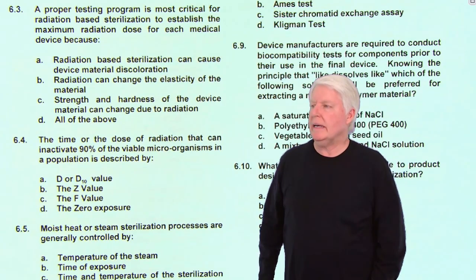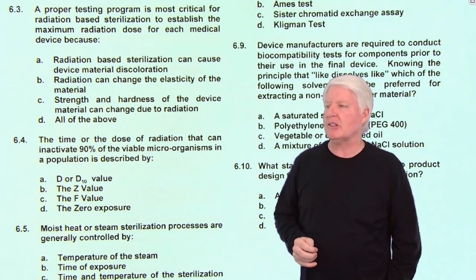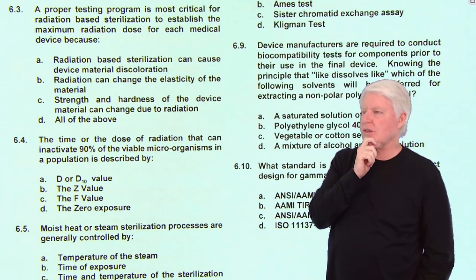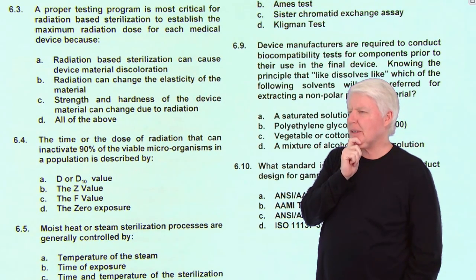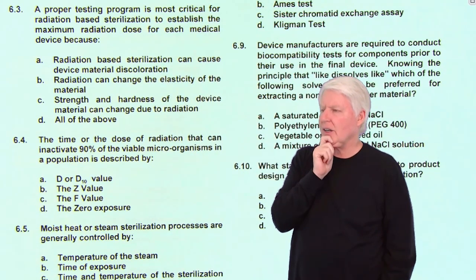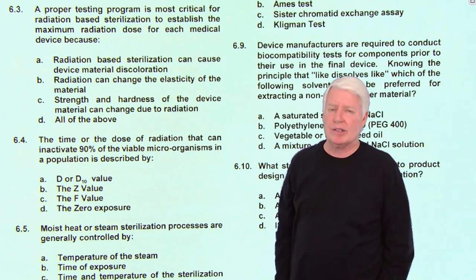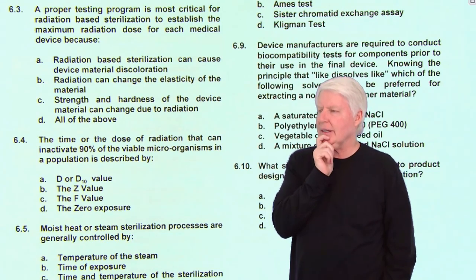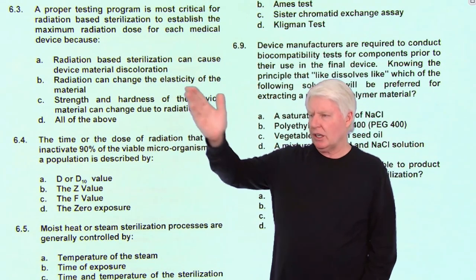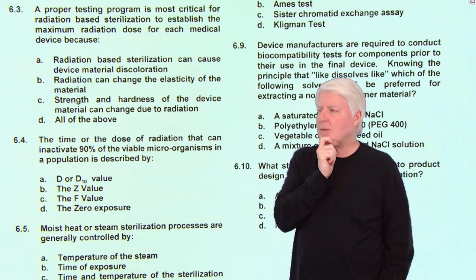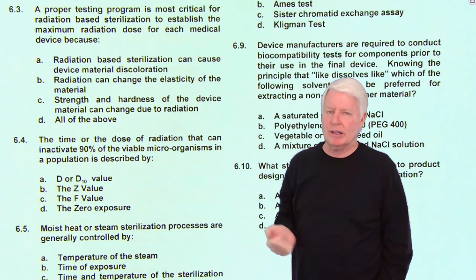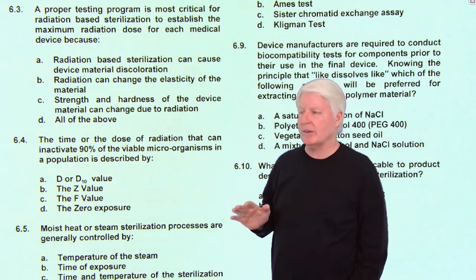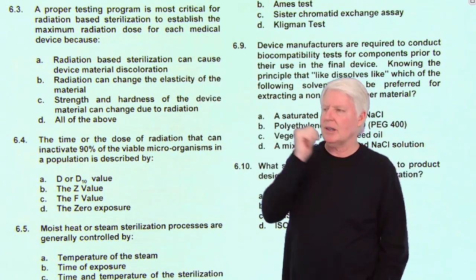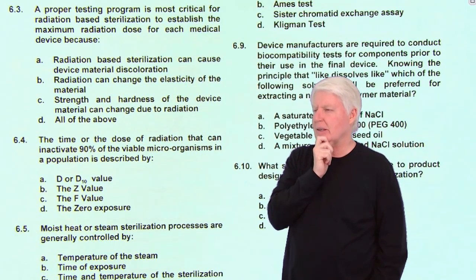Very good. All right, here we are at the next question. A proper testing program is most critical for radiation-based sterilization to establish the maximum radiation dose for each medical device because radiation-based sterilization can cause device material discoloration. For certain materials it does, and there are tables you can look up to see which materials discolor more than others. Radiation can change the elasticity of the material. Yes, it could. That's why radiation is not the best sterilization process for all materials. For some materials it's fine, for others not so much. But discoloration is pretty common, and that doesn't mean that it makes the material bad.